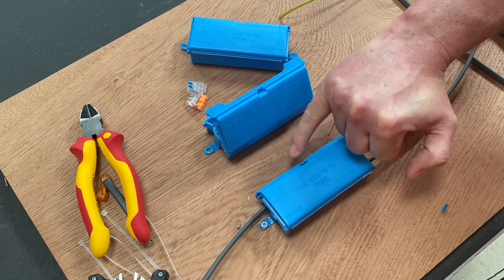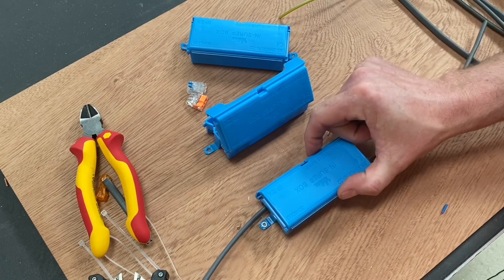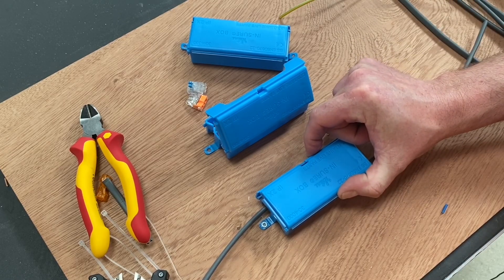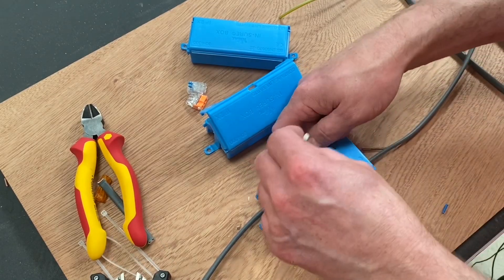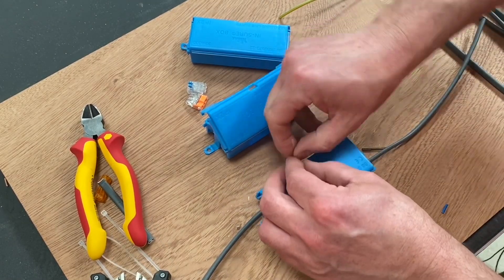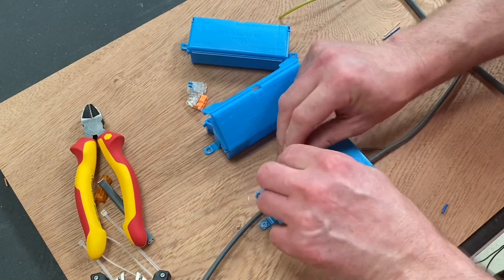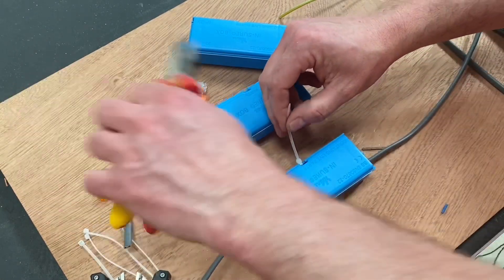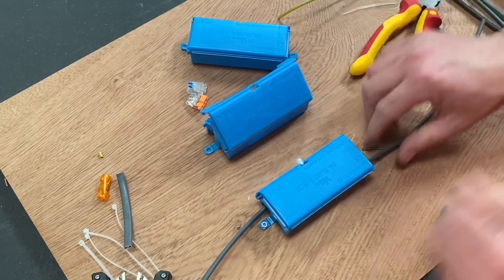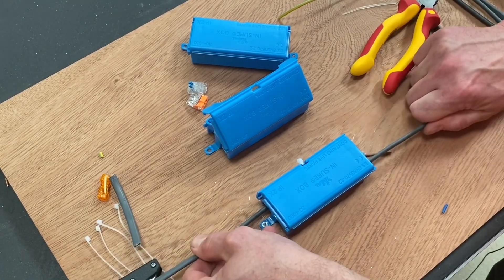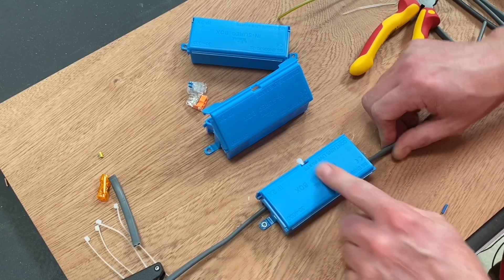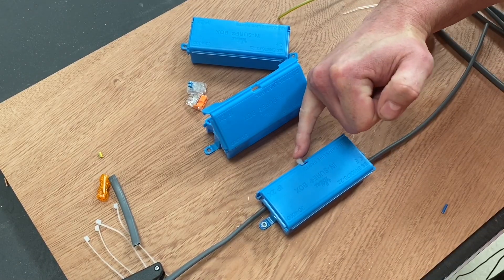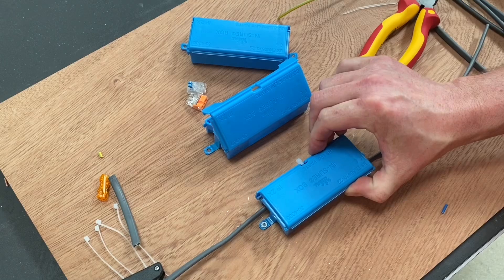And we've got a choice now if we want to put a cable tie through here in order to make sure that we can call it a maintenance-free connector. Let's just put that cable tie in as discussed, pop that through there, trim that one back off. So you can't pull those cables out. They're securely fastened between those grips, and our splice connections are in there, and now we have to get a tool in order to break that to get into the electrical enclosure itself.